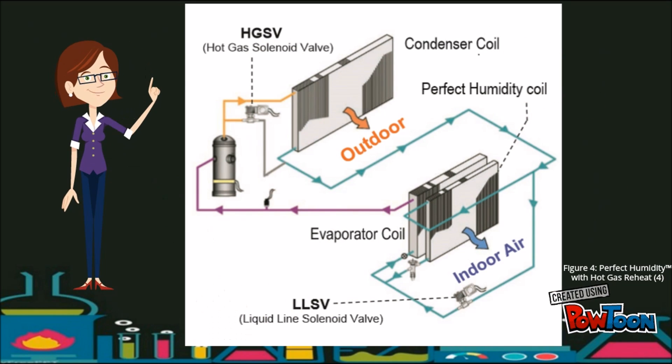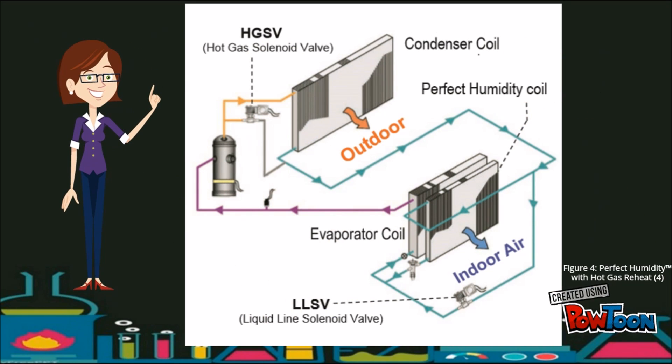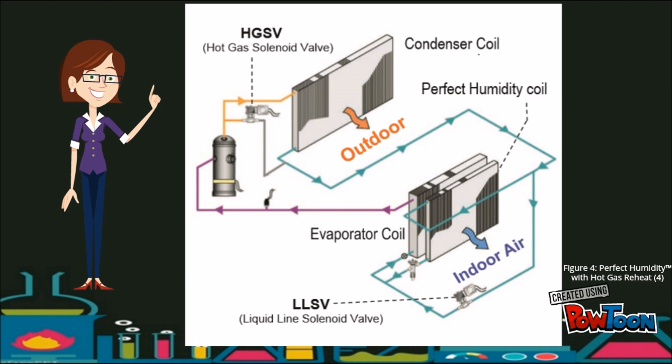When there is a call for dehumidification, a portion of the hot gas from the compressor bypasses the condenser coil and is fed into the liquid line.